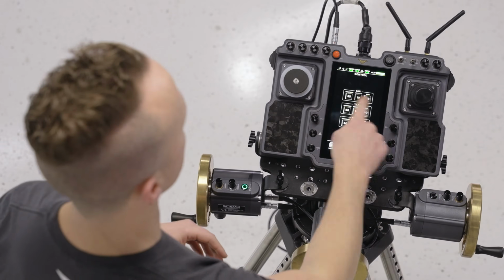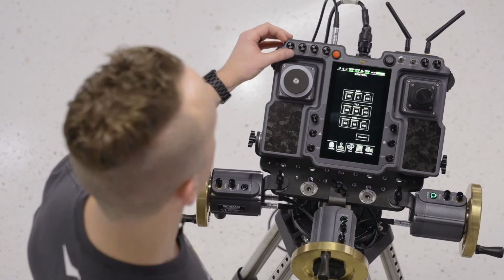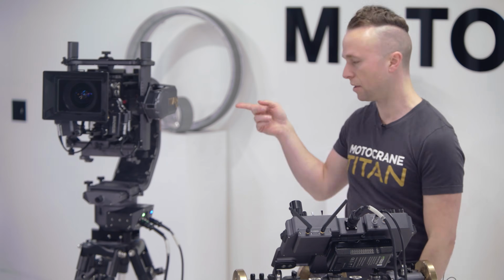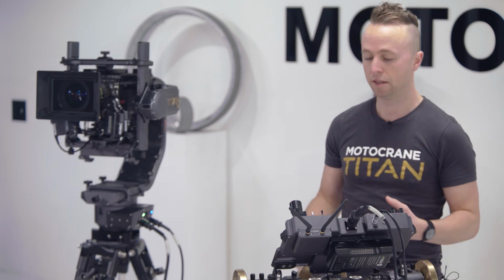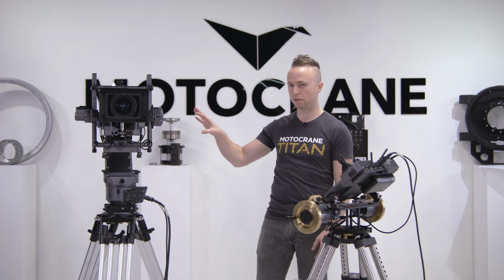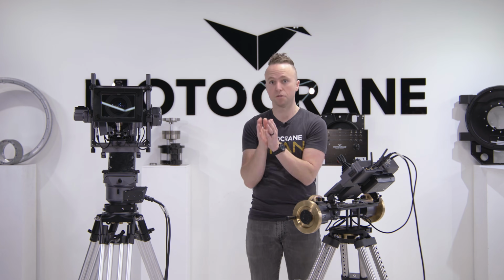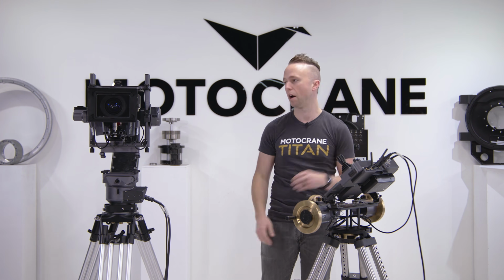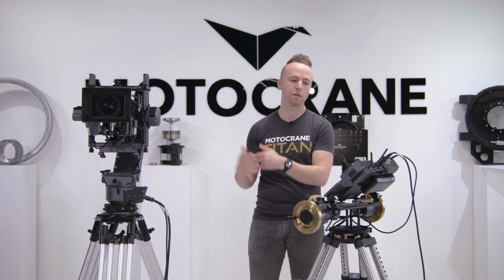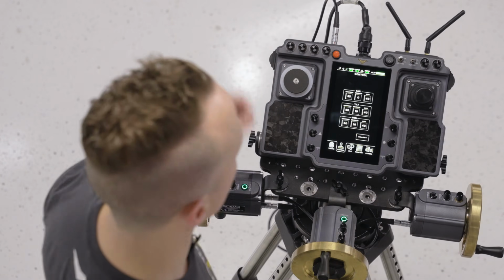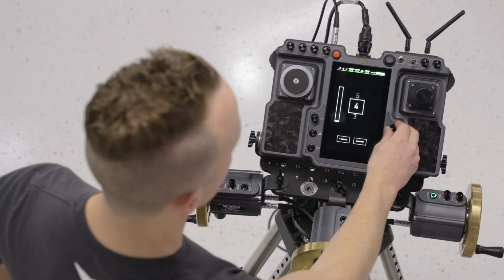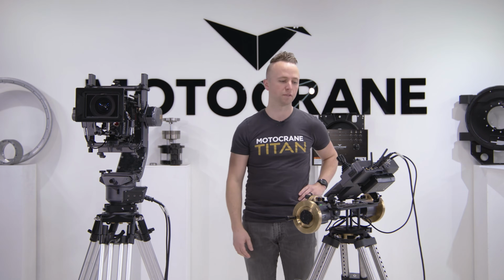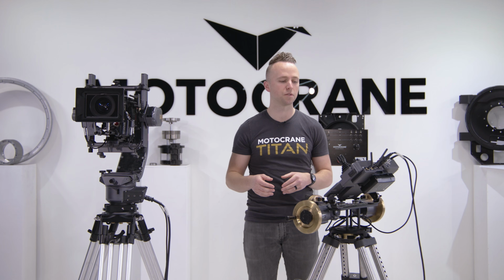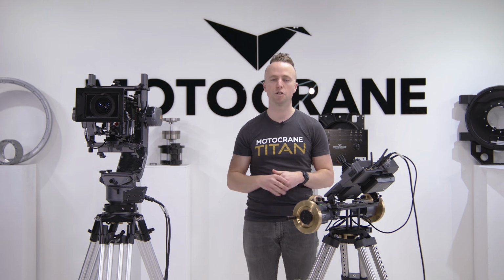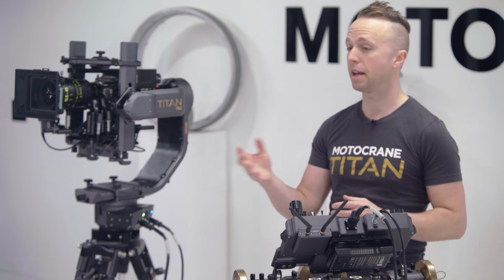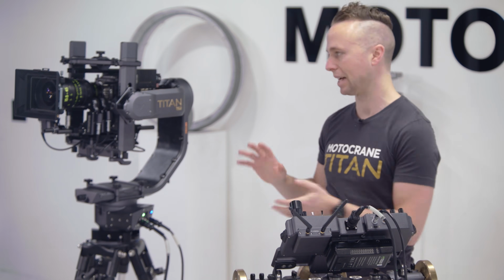So sometimes people will put their deadband down to 0. They'll have their speed turned up all the way, and there might be, as you can see here, a little bit of drift. This is not actually gyro drift - this is the system responding to a joystick command because there is no deadband, and I have my speed all the way up on the pan axis. So it's actually reading a joystick command right now. We can bring our speed back to a normal value, give ourselves a little bit of deadband, maybe around 5, and it's perfectly stable. A little bit of deadband is nice for mitigating issues with joystick command. We recommend having a deadband value of around 5 to 10 to make sure you're not accidentally commanding one of the axes.